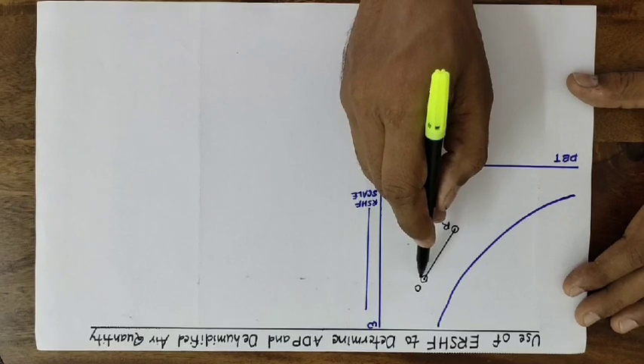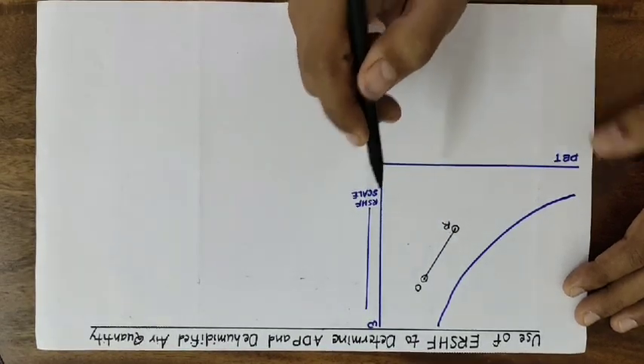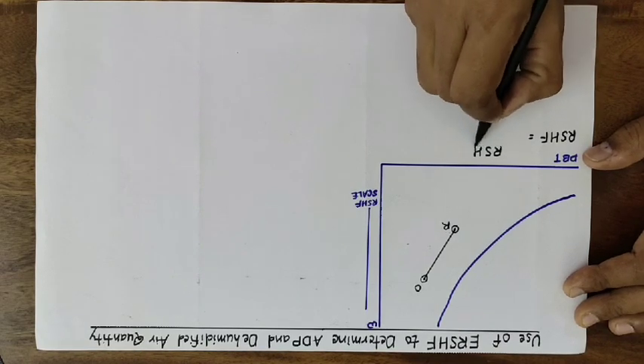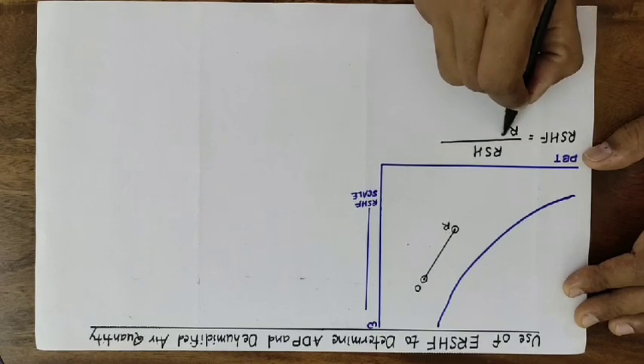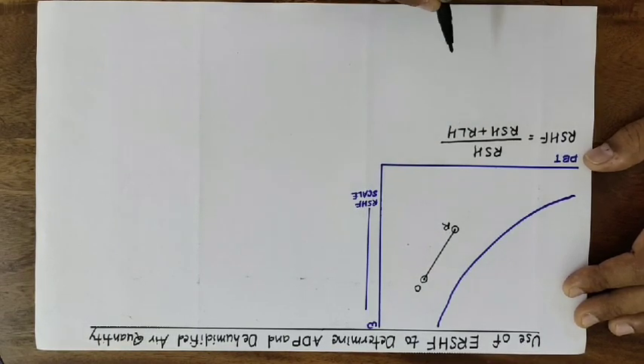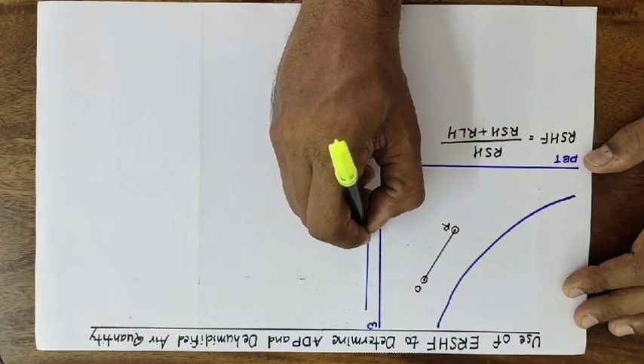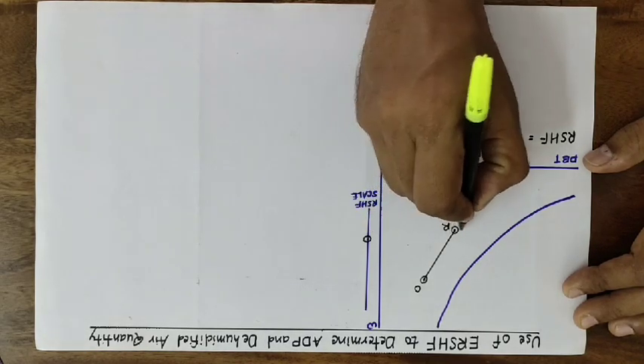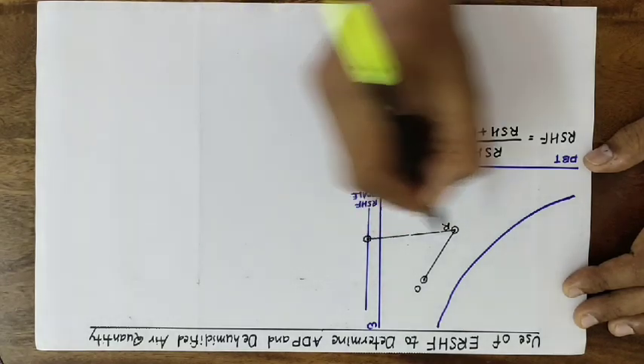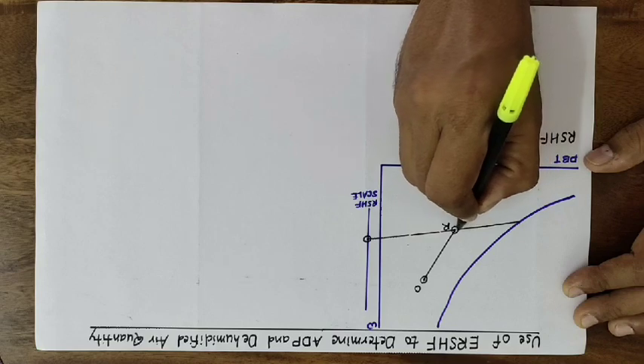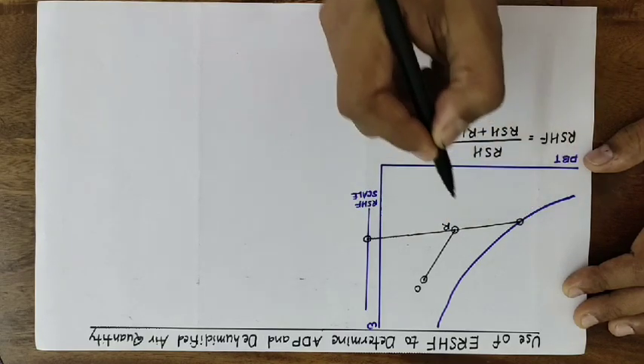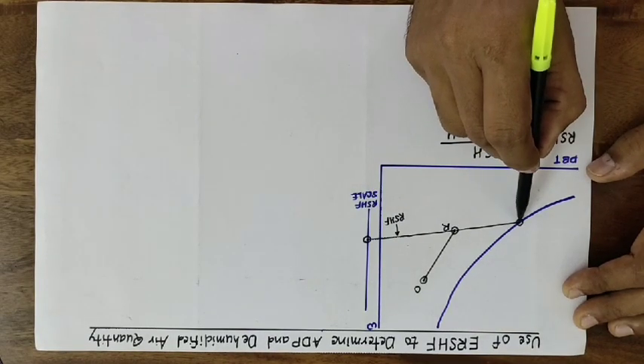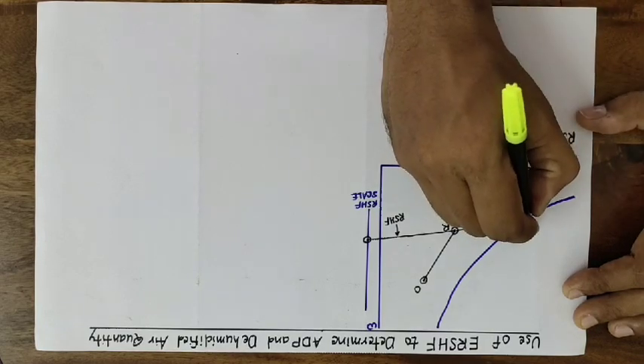Here I have the same picture on which the room air condition and outside air design condition is plotted. You can calculate the RSHF by the ratio of room sensible heat to the sum of room sensible heat plus room latent heat. Once you get this RSHF, you can plot this point on the RSHF scale on the right-hand side of the psychrometric chart and draw a line passing through the room air condition and this RSHF point, extending it to the saturation line. This line is called the RSHF line. This line intersects the saturation line at a point — remember, this is not the coil ADP; this is called the room ADP.